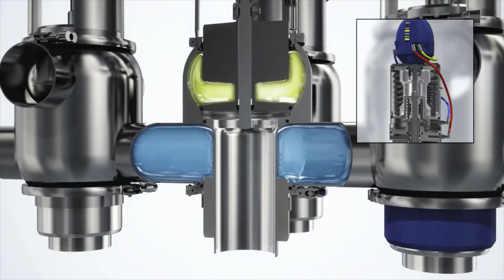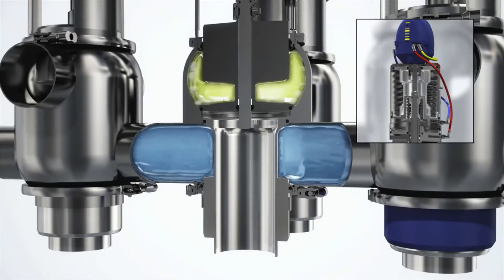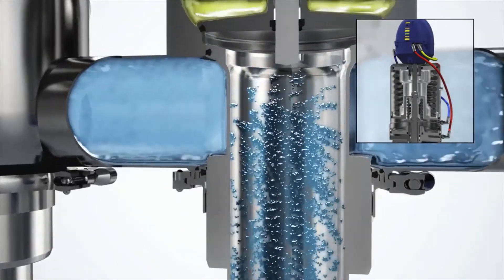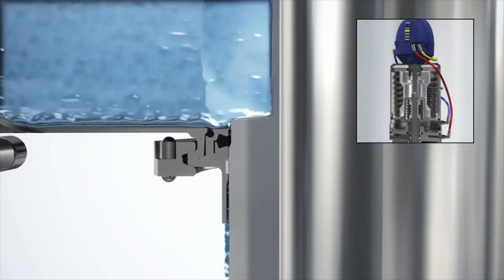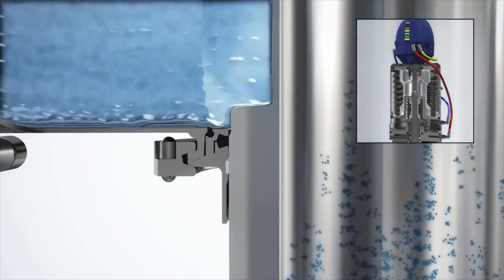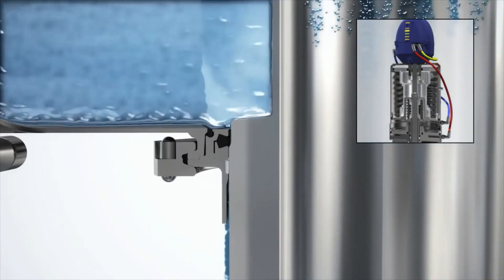Cleaning the outer diameter of the lower plug balancer is highly recommended, especially for processes carrying highly viscous products. The unique mix proof LP valve can be equipped with an optional lower flush to enable 100% cleanability of the valve through seat lift cleaning alone. This ensures that cleanability of the lower plug, both the internal and external surfaces, is in accordance with the 3A sanitary standards.